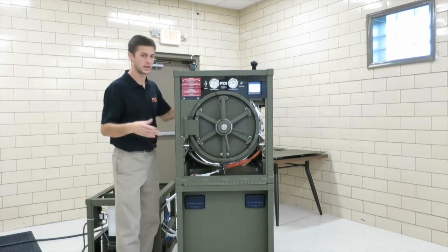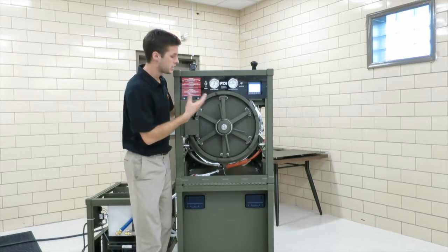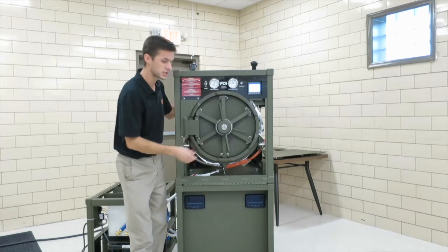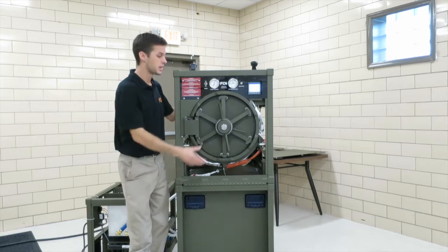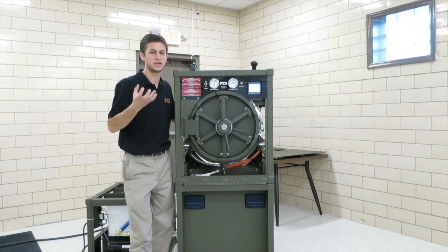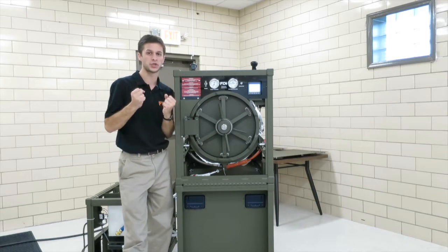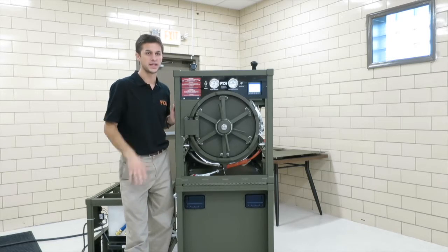Again, reference your technical manual. Sometimes the steam trap may not be operating correctly. There could be a steam leak that's not allowing the sterilizer to pressure up and heat up, so you may get that long heat up alarm.